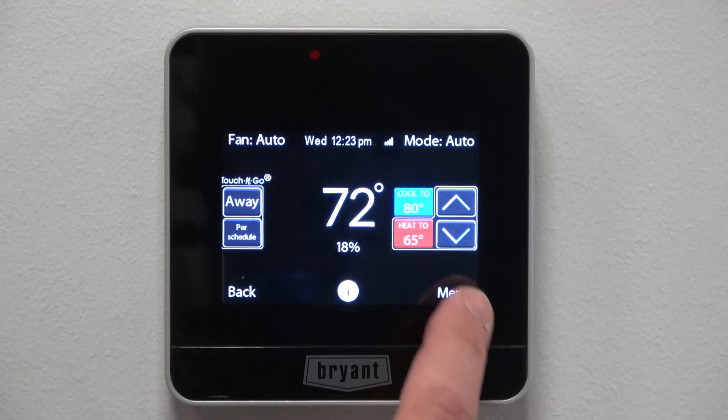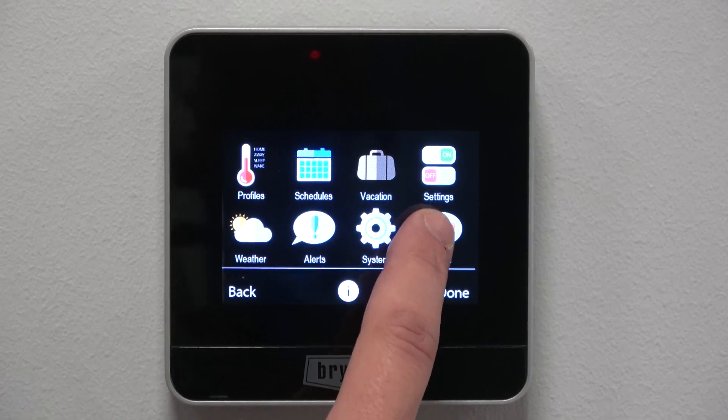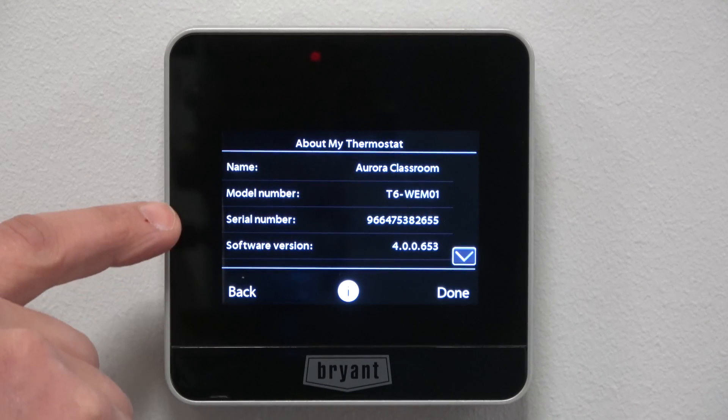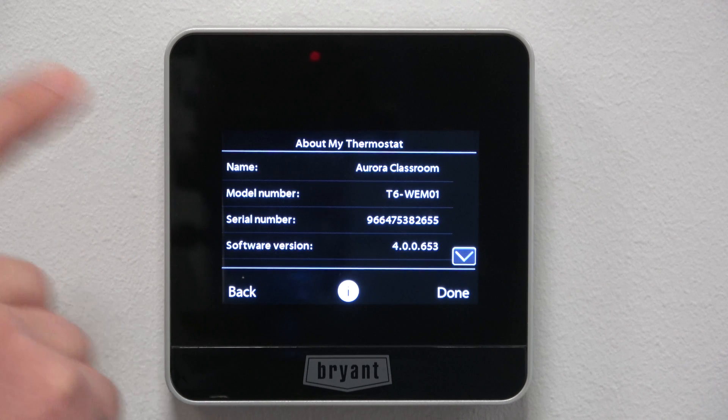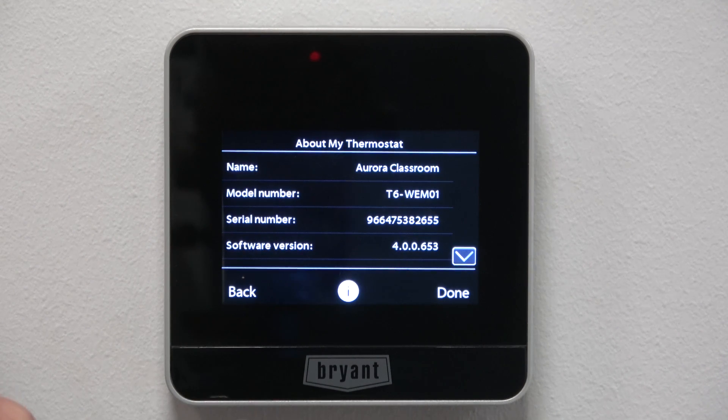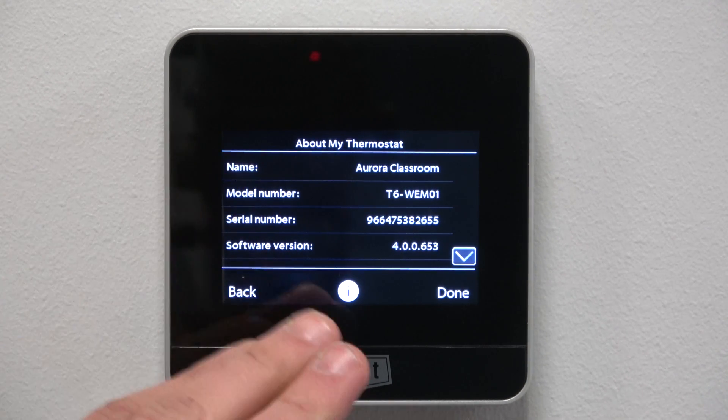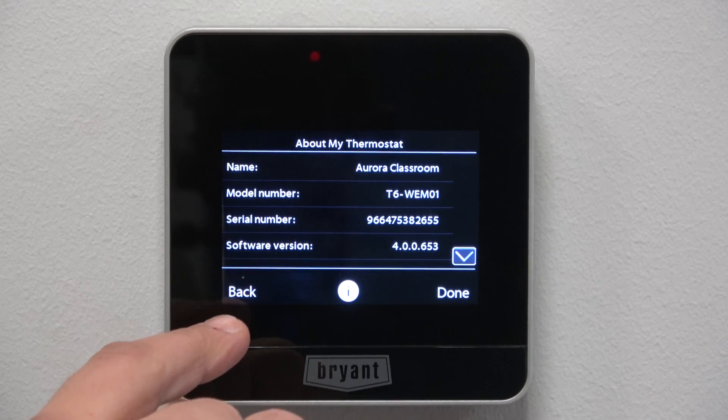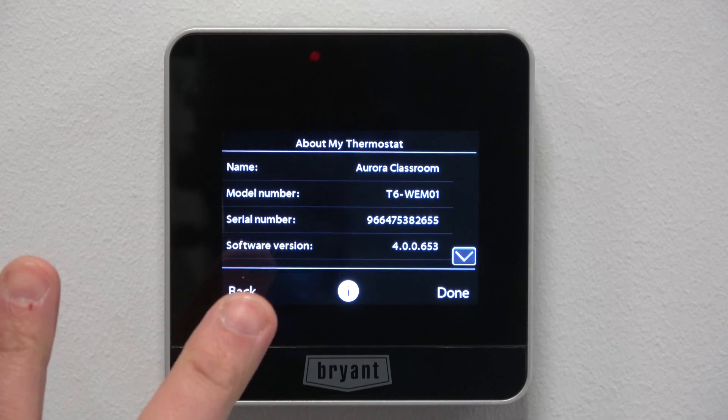On the Bryant Housewise carrier core stat, if we come into the menu and click on service and click on about, and there you'll see our serial number. That's what the portal is calling the electronic serial number. And then the newer versions of this stat, you'll see the serial number and below that you'll see the warranty serial number. You need both of those numbers.